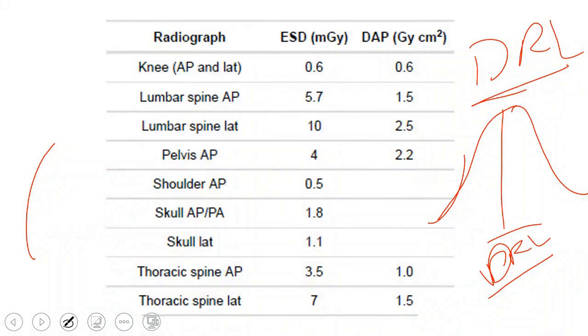If it turns out that your limit has increased, then at that time I need to conduct an investigation into why these cases have increased. Could the cases increase? Yes, they could, but there must be a reason for the increase in doses. Now I find that I can perform another optimization and reduce the reference dose level again, create a new reference dose level, and work on it. The reference dose level can be established at the level of the radiology center, meaning a place or institution, or it can be done at a national level across the entire country, or it can be established among multiple hospitals.